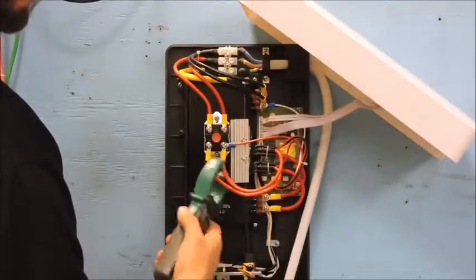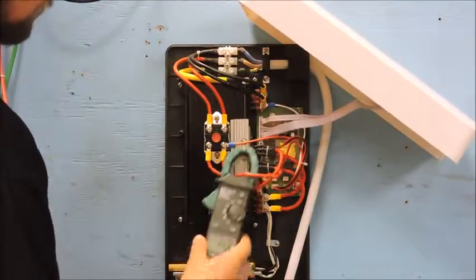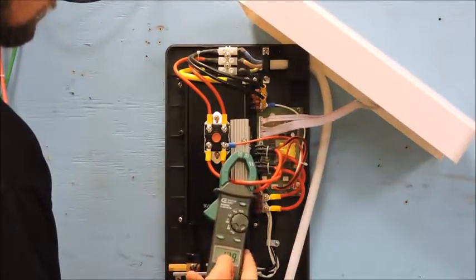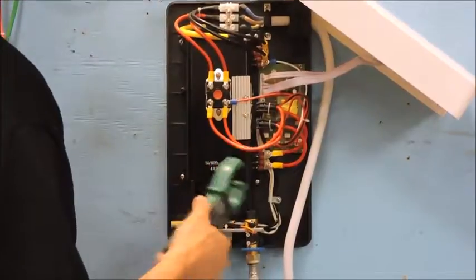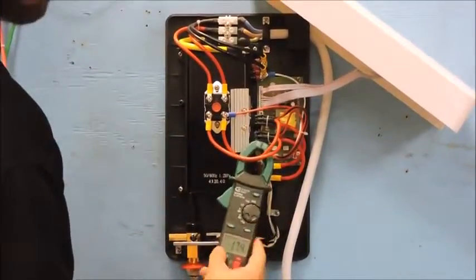If you have an amp meter, you can read the amps by clamping over each individual wire leading to the overheat sensor. With max power, neither side should read more than 25 amps.